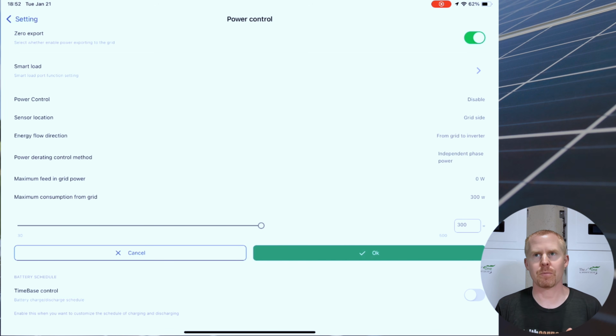So when you're in a self-consumption mode and say you do not have an interconnection agreement with your power company, this value allows your inverter to always draw a certain amount of power from the grid so that if a large load turns off, it's not instantly going away and then allowing some power to get pushed back up to the grid. By default, it's a 300 watt draw. Looks like you can go from as low as 30 watts up to 500 watts. This was one reason why I actually switched over to using the generator as my grid feed, because I didn't want that power draw always coming from the grid.